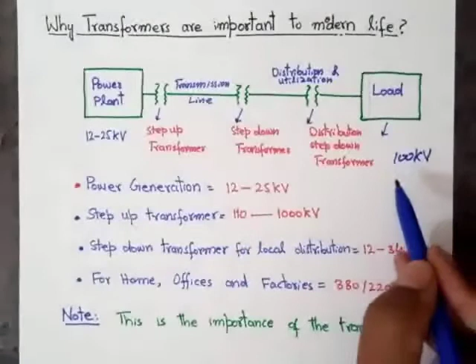It is not possible to generate 100 kilovolt, 200 kilovolt or 500 kilovolt because it is not economical, and also it is very difficult to design generators of such a large size. That's why in modern power plants the generator basically generates voltages within 12 to 25 kilovolt. After this we use a step up transformer. A step up transformer basically steps up the voltages from 12 to 25 kilovolt to 110 to 1000 kilovolt.